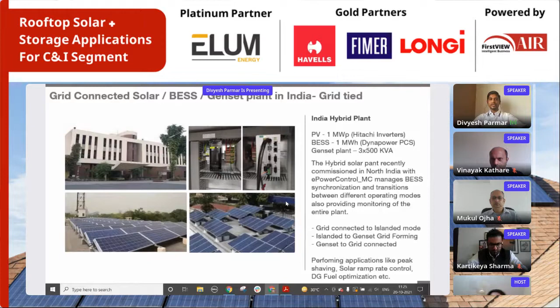Here we have deployed our e-power control MC, managing different operating modes like grid connected to islanded, islanded to genset grid forming, and genset to grid connected. We are performing peak shaving, solar ramp rate control, and DG fuel optimization functions.